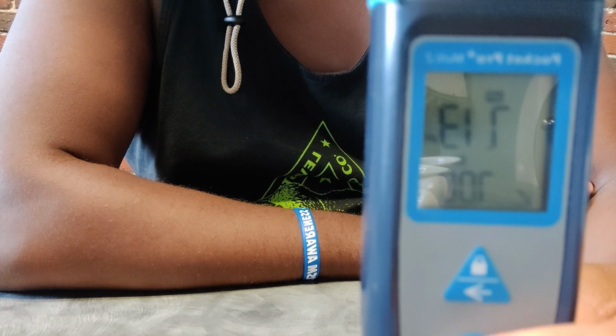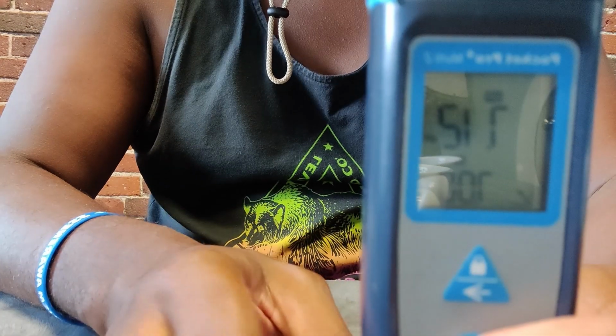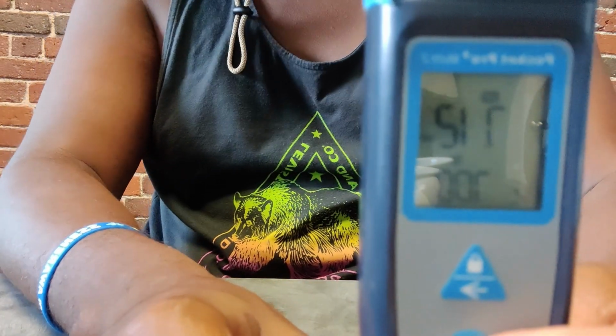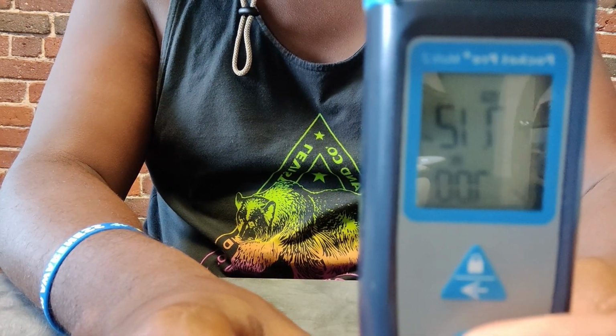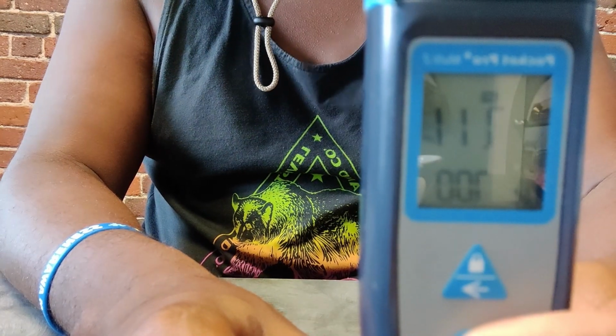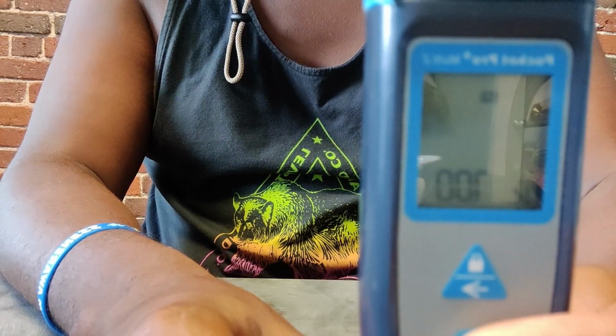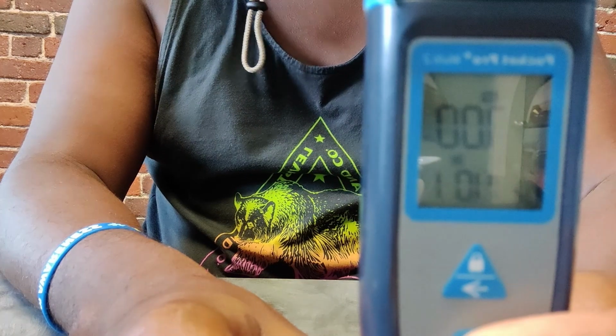Take your data sheet and in the reading before pH calib box, write down whatever number this is that the machine has settled onto. In this case, 7.15. Press the middle button. The reading on the top row will now flash 3 times, confirming that the machine has accepted this reading.